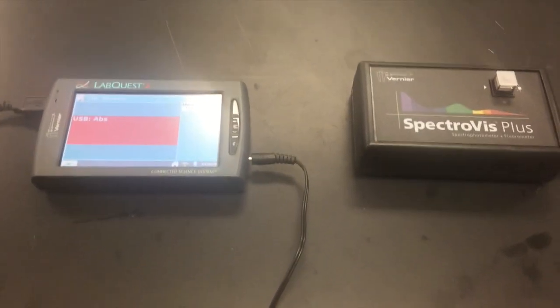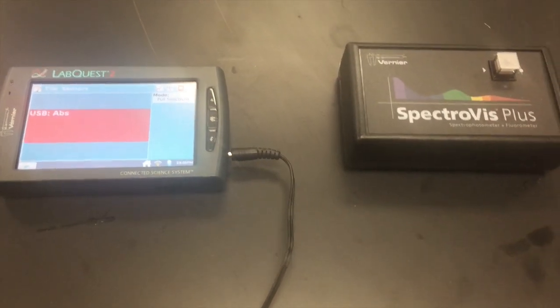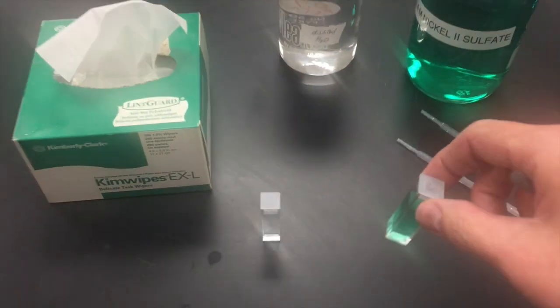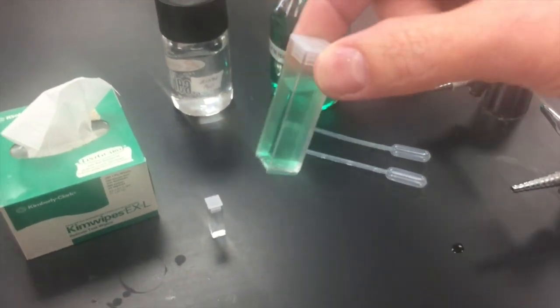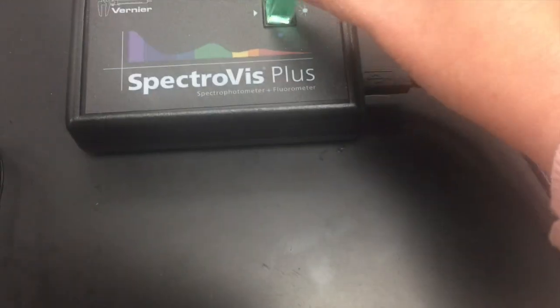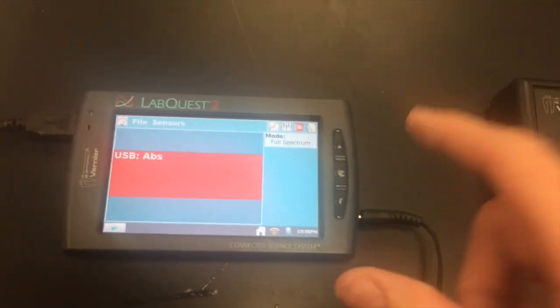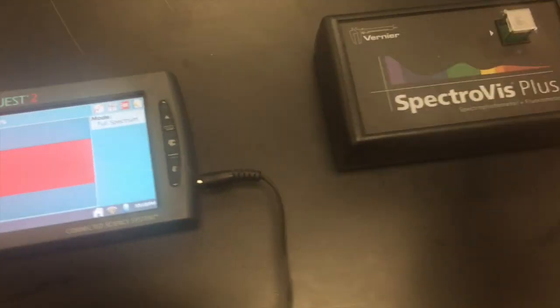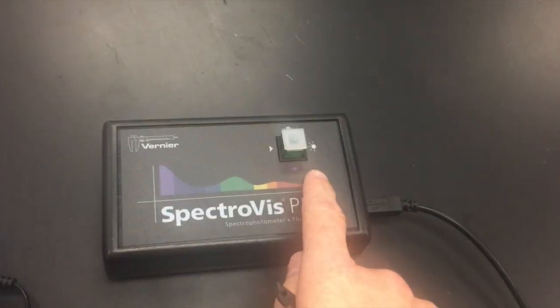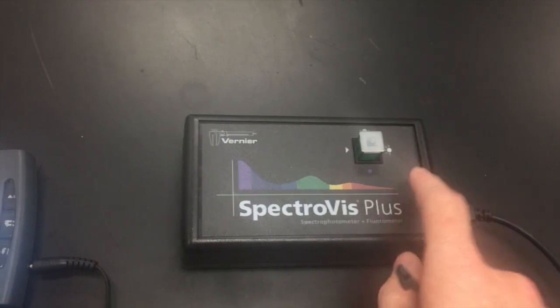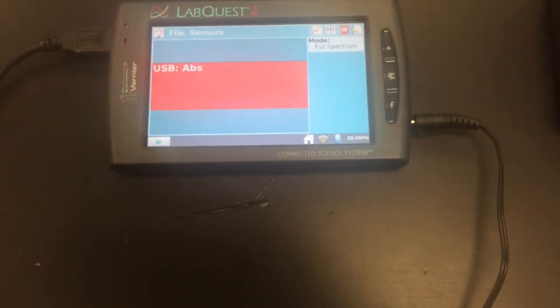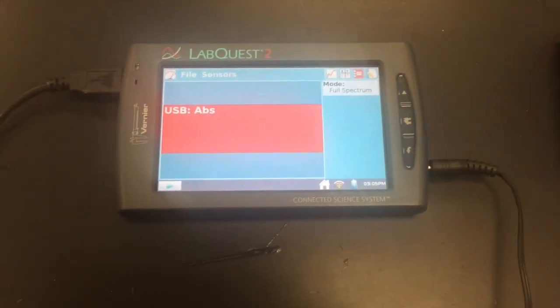Now that our spectrophotometer is ready to use, what we want to do is actually measure the absorption of light of the sample that we are interested in. So I'm going to take out my blank and put in a sample of my nickel 2 sulfate. Nickel 2 sulfate is a lovely green color. The first thing we're going to do is put it down into the spectrophotometer. This time we don't need to calibrate, but we want to read what the absorption is for the light that's traveling through this cuvette.